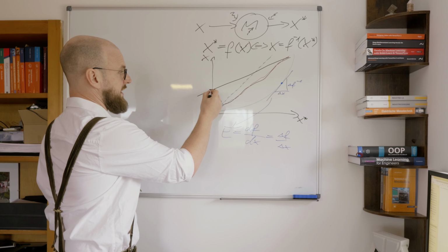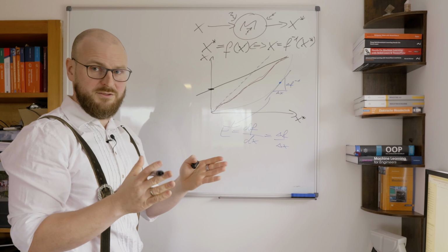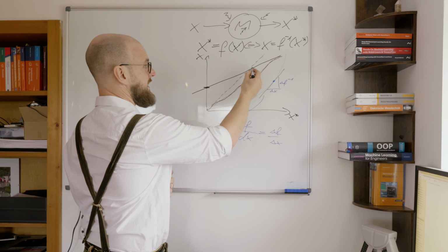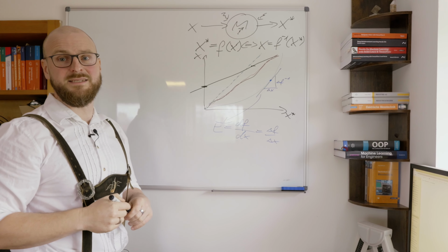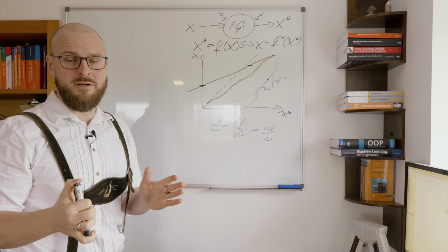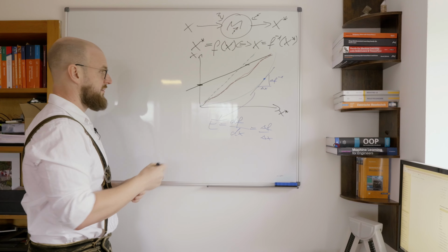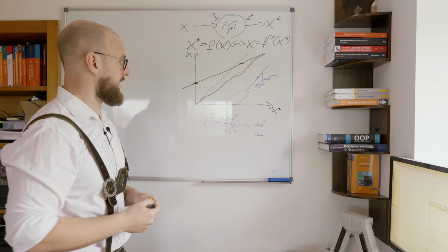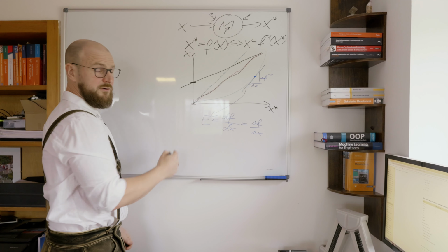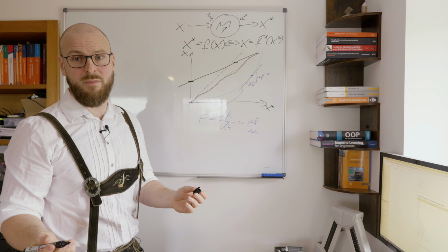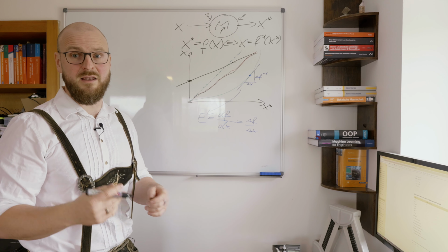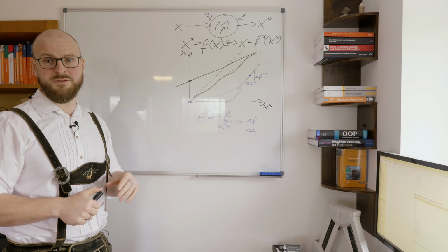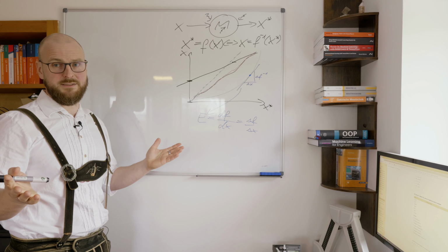When nobody is within the light barrier, it will give you a value, and it will give you a value when somebody is in the light barrier. You ensure that you can recognize if that light barrier is defective. Meaning, when it's not working, it would give you a value of 0, and by that you know it's defective. So that live zero point is an important thing you can use in all practical senses.